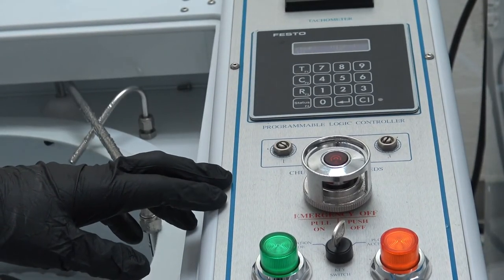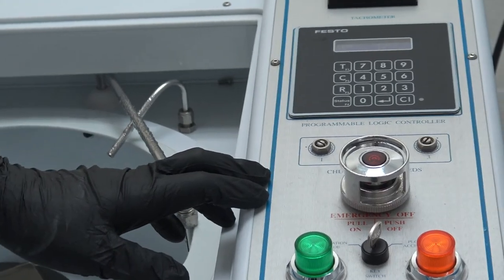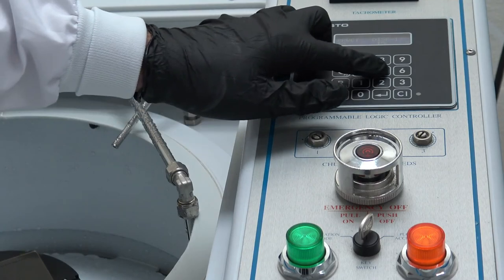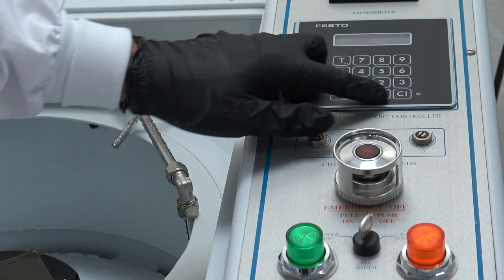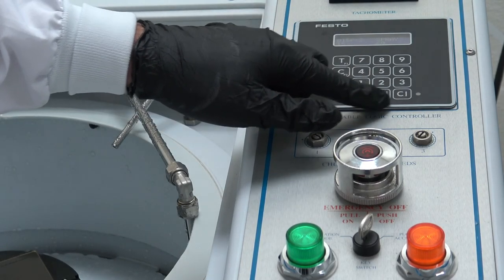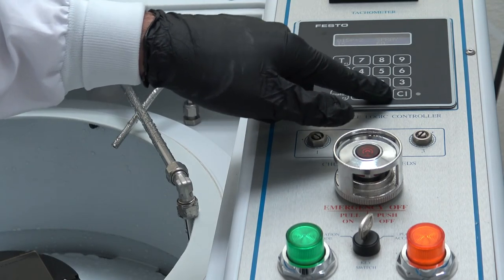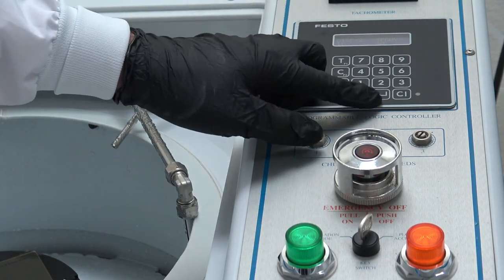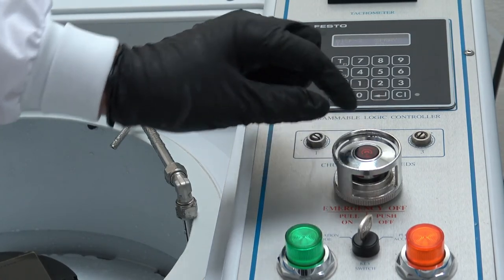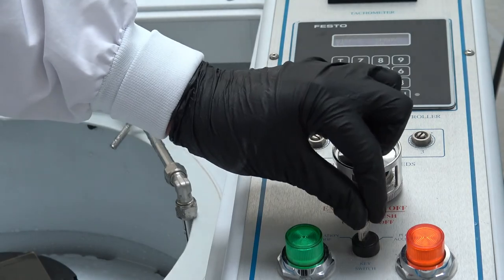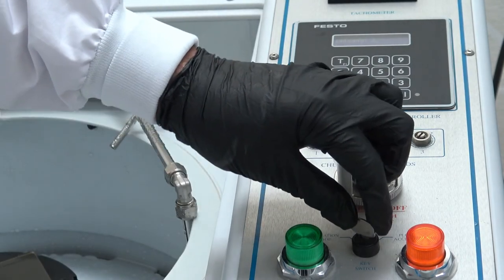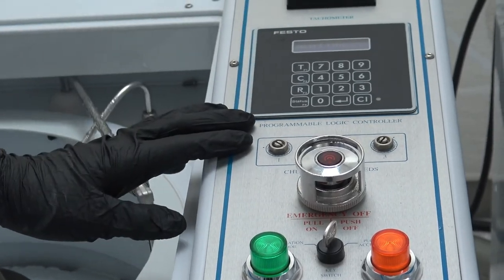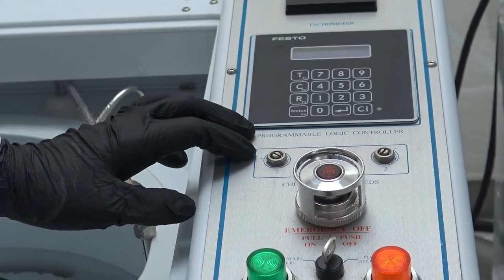Now we have dispense 1. This is the amount of time for the surfactant dispense. A typical time for surfactant dispense would be around 5 seconds. So let's go ahead and do 5. I pressed the wrong button right there. So what we'd have to do is actually, if you want to adjust the recipe back, you'll have to just start over. So you turn the operation mode, and then you switch back to PLC mode. We're already in recipe 2, so we're going to go ahead and do the recipe edit function again.